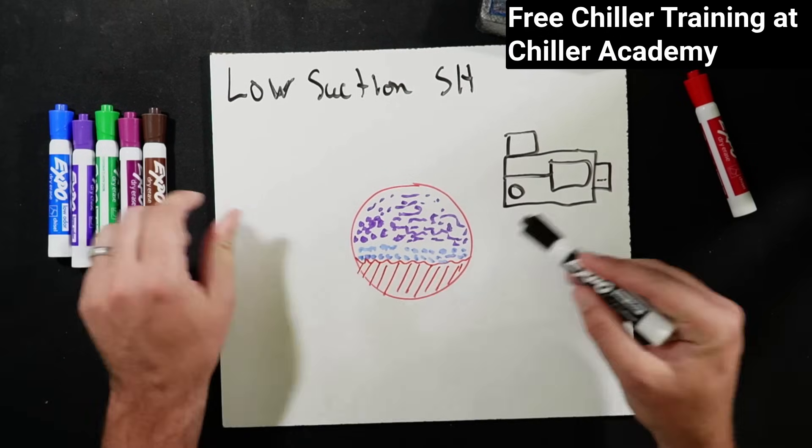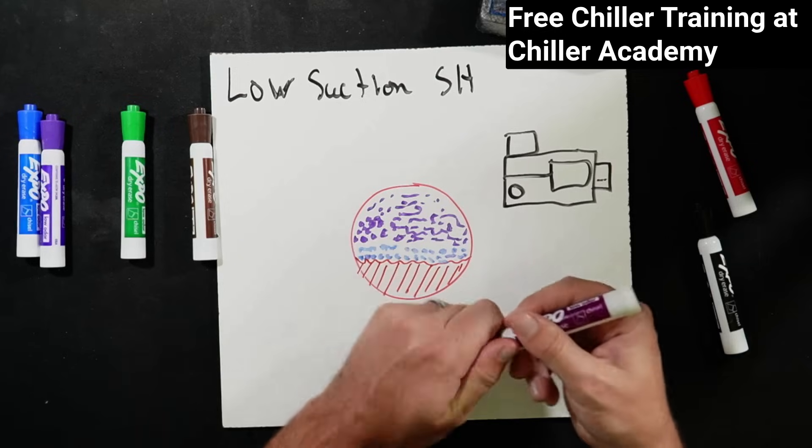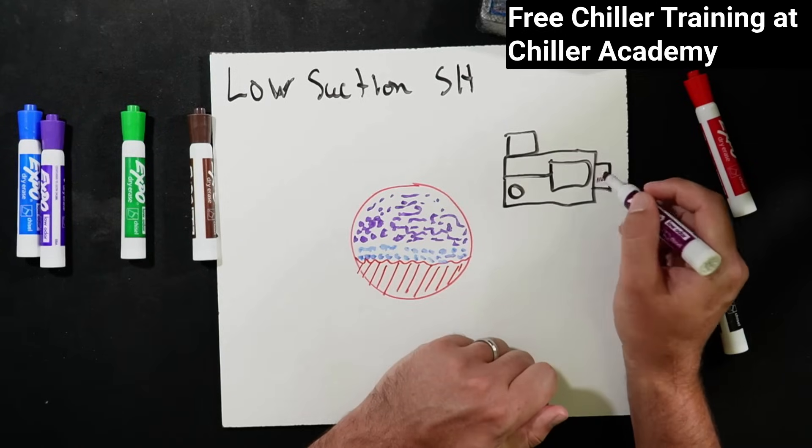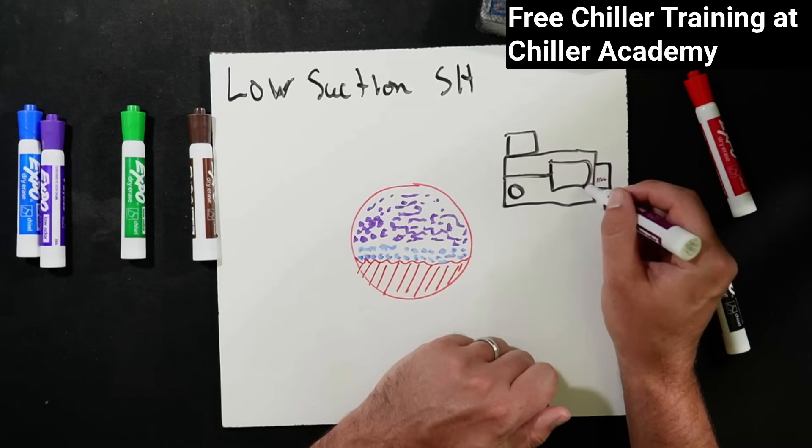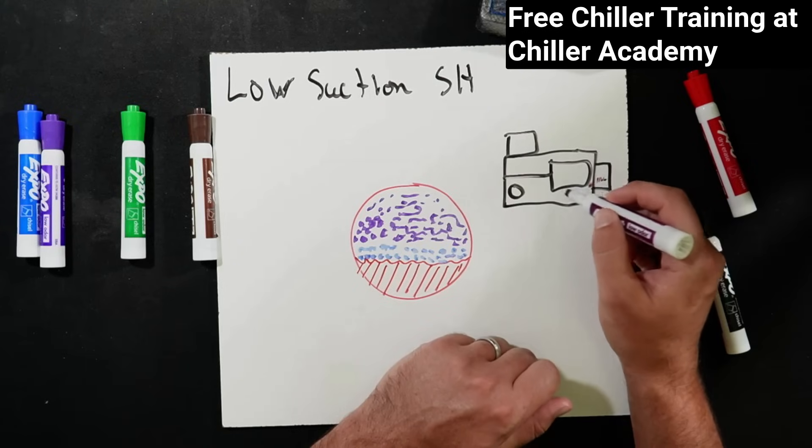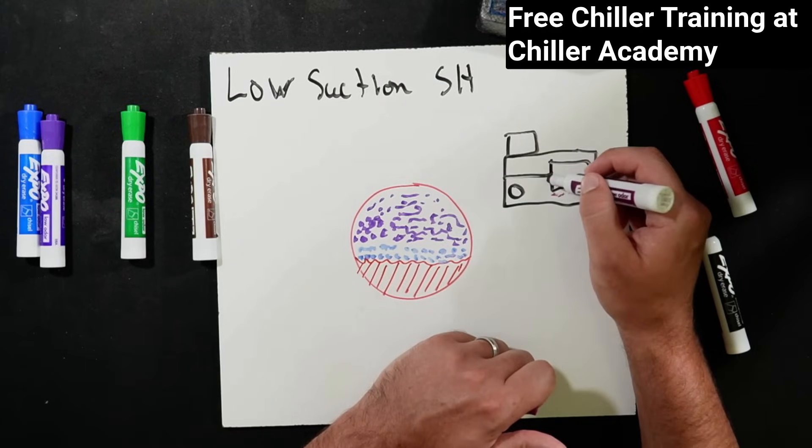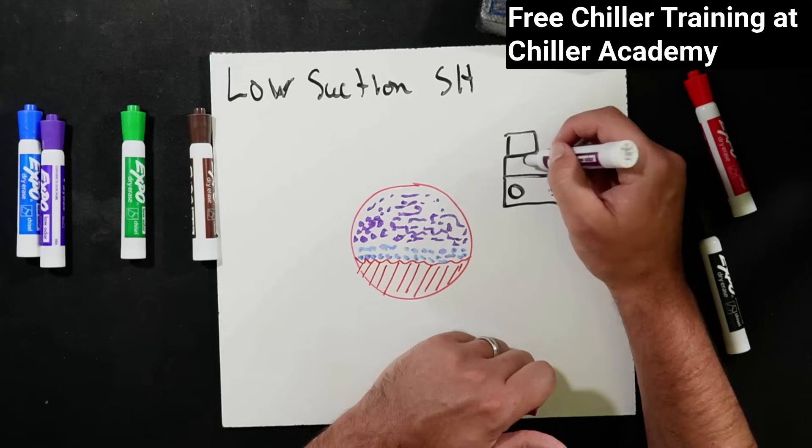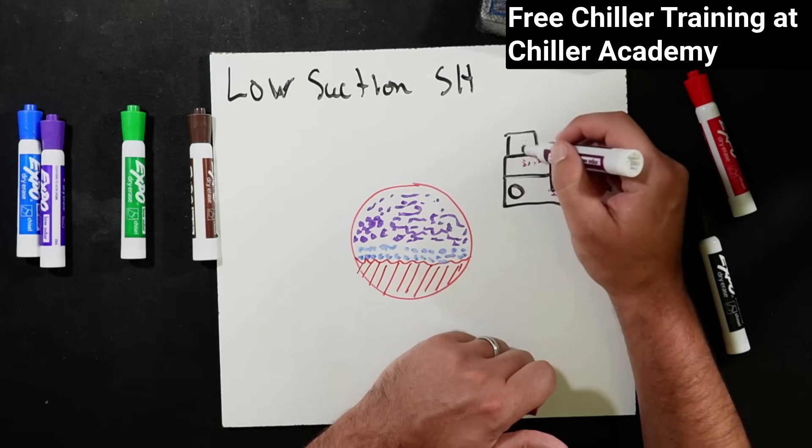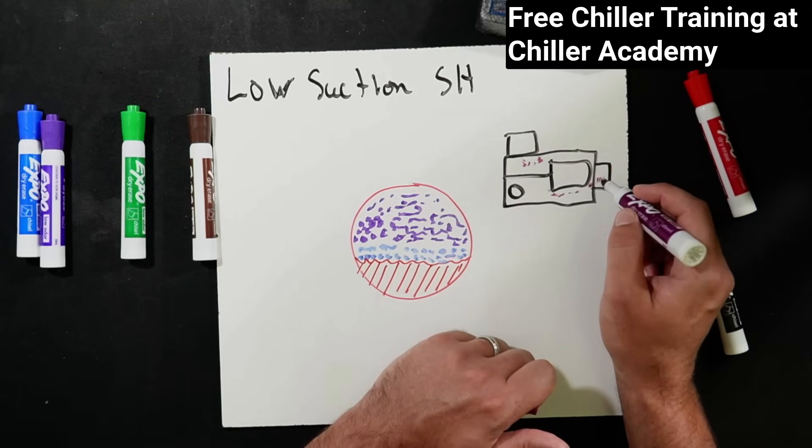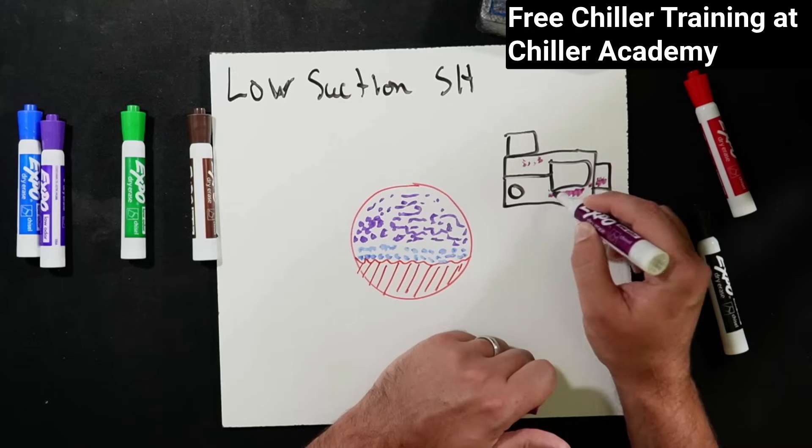So as that liquid refrigerant comes in, I should probably do a different color. We are going to see it come into the bottom of the suction line is going to go through the stator and motor because that's part of how these compressors are cooled. And then if it was a gas, then it would get just drawn up as a vapor up into our head, but that's not what's going to happen with this liquid refrigerant.